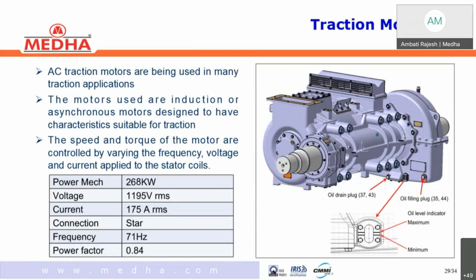Otherwise, yearly once we need to replace the complete oil, and we need to top up the grease for the traction motor. Both end bearings are there, drive end and non-drive end, and even the MSU should be topped up with grease. Only the gearbox assembly needs the complete oil replaced yearly once. The major schedule is for 6 yearly once. Till 6 years, there is no major attention required in the traction motor, only topping up and oil replacement yearly once.